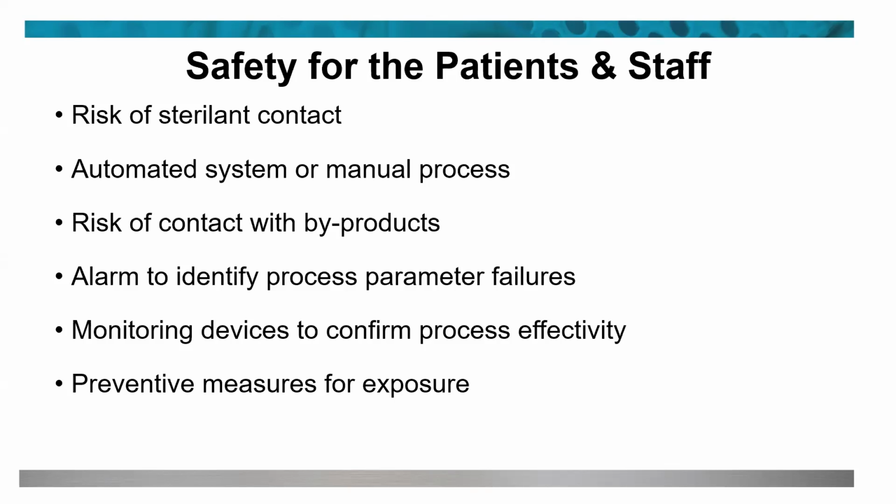What kind of risks are you going to take to have any kind of exposure to the sterilant that you might have? You think that it comes out dry and you don't need to put gloves on, but you really should be wearing gloves, as I mentioned earlier, anytime you're dealing with any kind of liquid chemical sterilant, because there may be a little bit left on there. And some of this, you think, oh, it's hydrogen peroxide. Well, the concentration levels are so high that it really could do some damage to your skin if you get burnt with it.